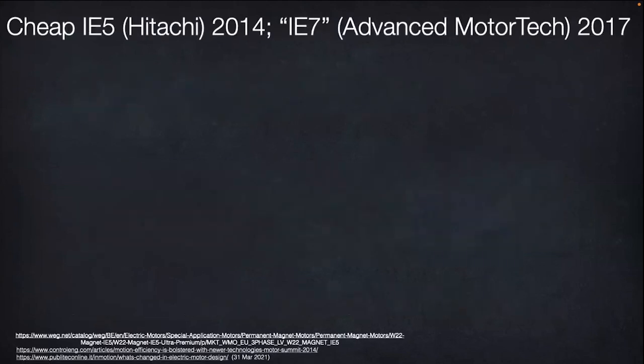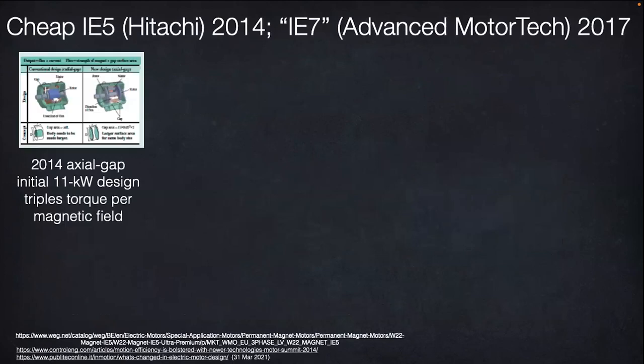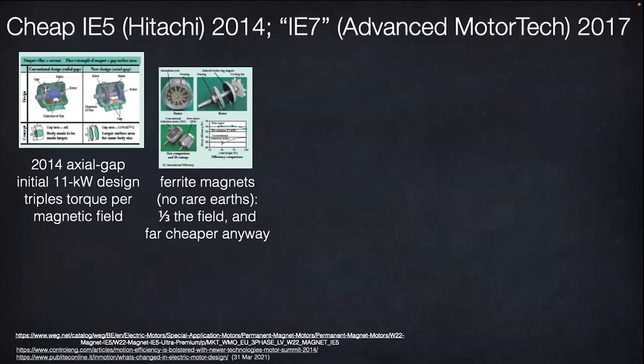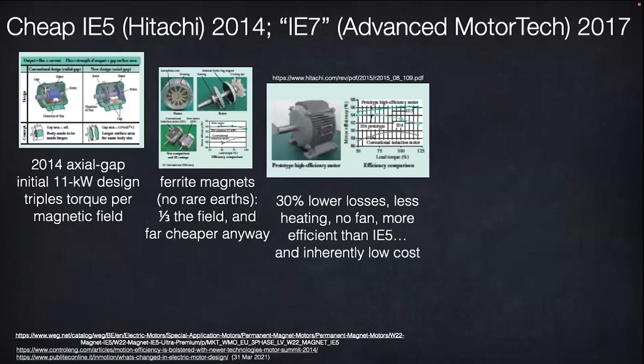More recently, better design has made the most efficient motors a lot cheaper. In 2014, for example, Hitachi designed a short axial flux 11 kilowatt motor whose amorphous iron core cut the iron losses 90%. The cheap ferrite magnets could then get the same torque from one-third the field strength. The 30% lower losses eliminated the cooling fans, saving more energy and downtime.